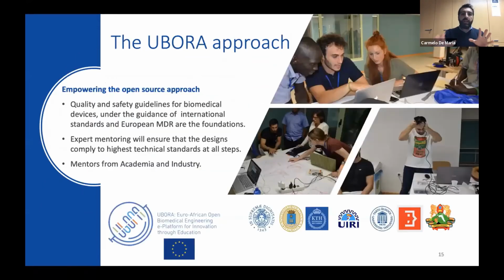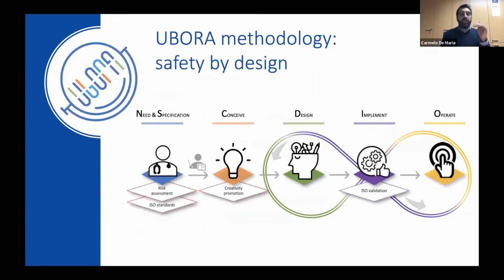So this is the way, and in UBORA we try to promote the design for prototyping of those devices in a structured way, so that you will never forget any point that is necessary for certification. During the project, we try to include the safety of the device directly in the design. We use it like a methodology. The name is important just for some people, but there are many ways in which you can develop a medical device. There is biodesign. There is the method called CDIO: conceive, design, implement, operate.